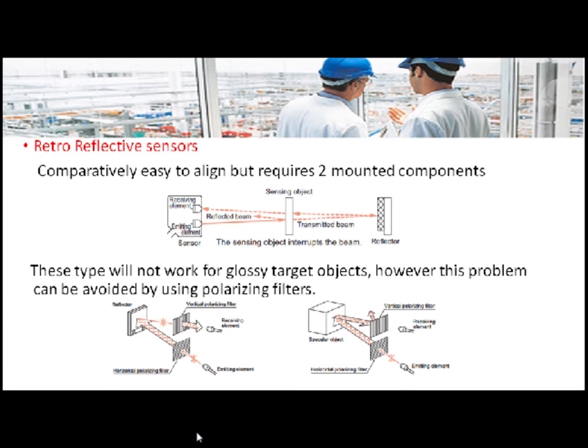The next type is retro reflective type optical sensor. Compared to through beam type, it consists of a single module that houses both the emitting and receiving elements. It also consists of a reflector used for reflecting the light in the absence of the object. However, the problem with this type is that whenever a glossy or shiny target is present, it itself will act as a reflector and send a wrong signal to the receiving element.